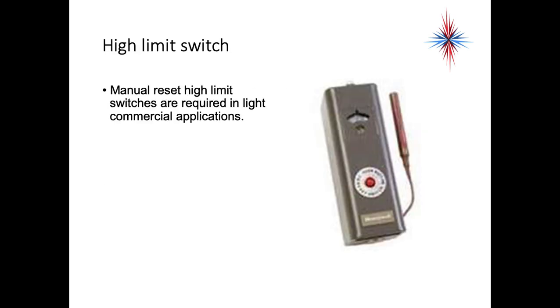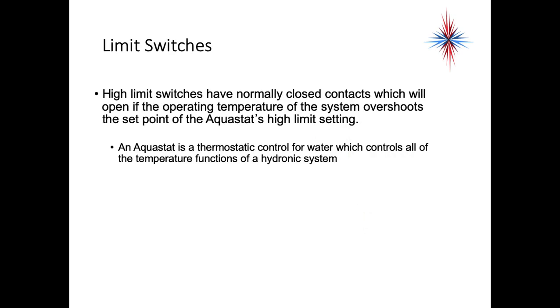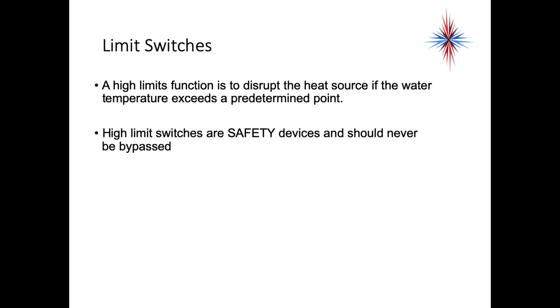This is an example of a manual reset high limit switch — it's required in light commercial applications and this one actually straps onto a pipe. The high limit switches have a normally closed contact which will open if the temperature of the system overshoots the set point of the Aquastat's high limit setting. An Aquastat is a thermostatic control for water which controls all of the temperature functions of a hydronic system. A high limit function is to disrupt the heat source if the water temperature exceeds a predetermined point, and high limit switches are safety devices and should never be bypassed.